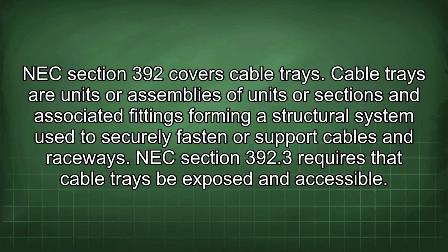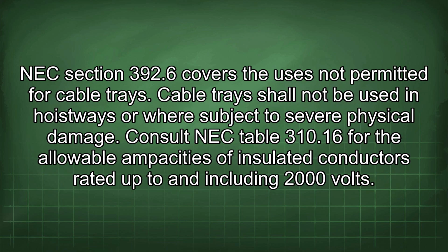NEC Section 392 covers cable trays. Cable trays are units or assemblies of units or sections and associated fittings forming a structural system used to securely fasten or support cables and raceways. NEC Section 392.3 requires that cable trays be exposed and accessible. NEC Section 392.6 covers the uses not permitted for cable trays. Cable trays shall not be used in hoistways or where subject to severe physical damage.